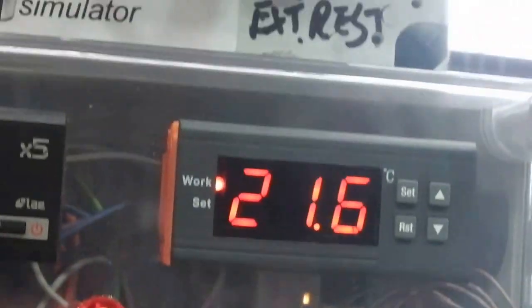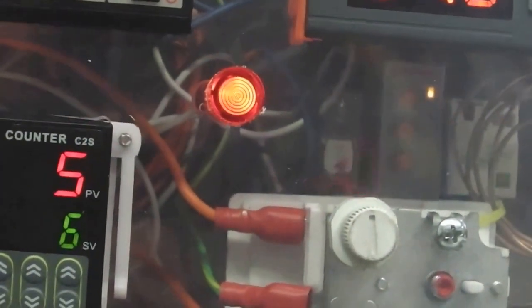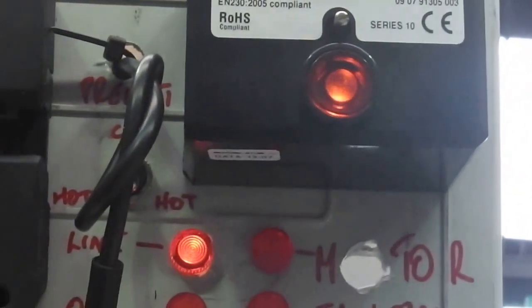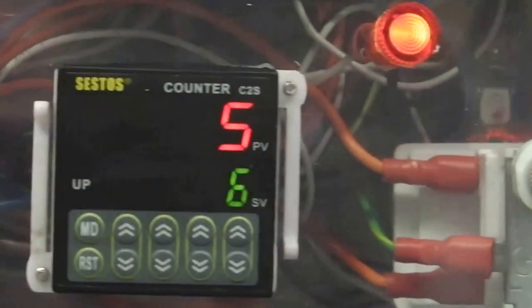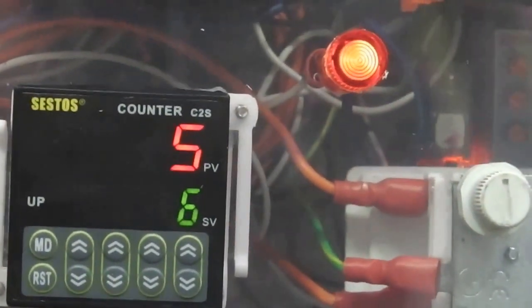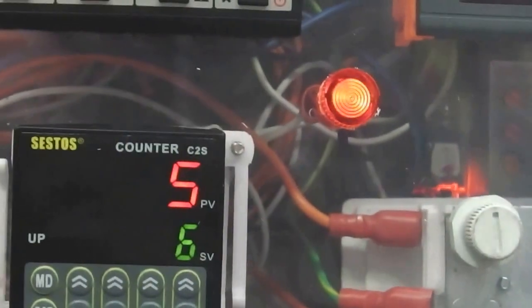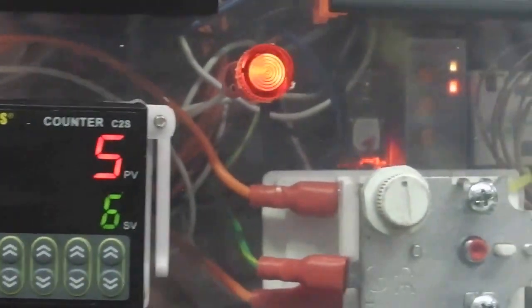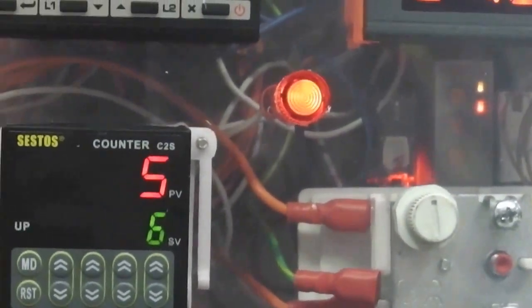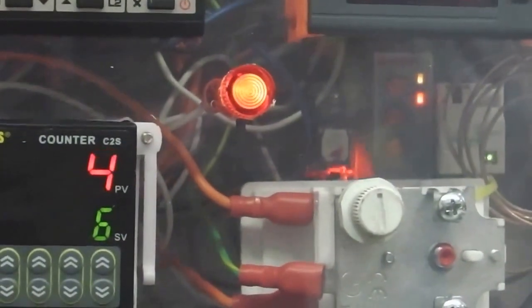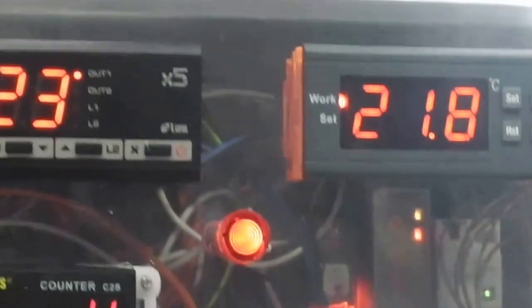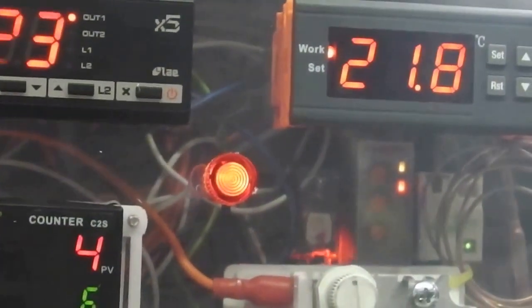And we blink away. So now it's having another six attempts to do automatic restarts. So the whole idea of the Sestos counter is to prevent any damage to the burner gun being controlled by multiple automatic restart attempts. Okay.